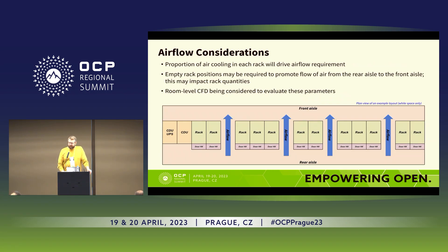We have made some airflow considerations, because the air that goes into the rack through the heat exchanger has to go through the front and back as well. The suggestion was to crisscross the racks so that we have cold front aisles, letting the servers do all the work. We will test that out — the four slots that are currently openings to move air through them can be closed with our servers, and we could potentially hit one megawatt per modular data center, which would be quite substantial.